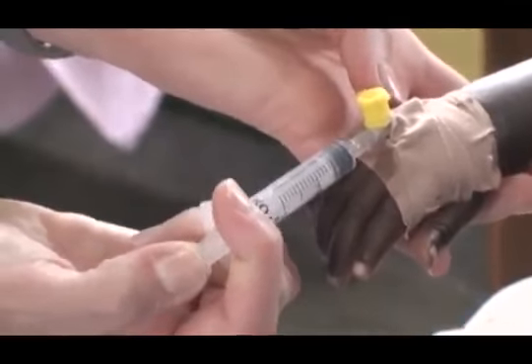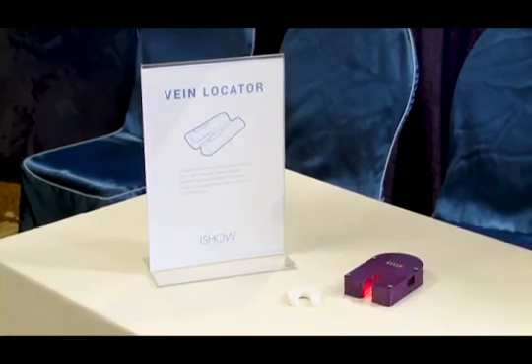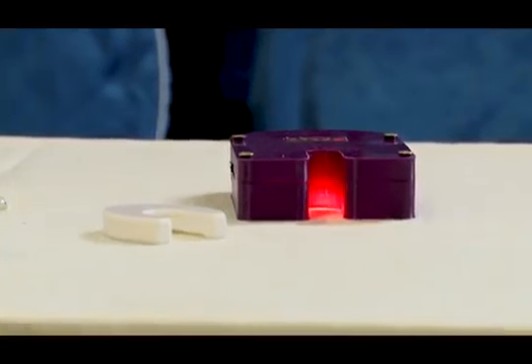The prototype was heating, so they told us for babies we should find a way of eliminating the heat. This is a device that will be put on several babies, so we should make it from material that can easily be disinfected. They also told us babies are not simple people to work with — they always flap and fly around. It would really be nice to make this device from very strong materials so that even when it drops it can keep working. Nobody has something like this out, so this could be your uniqueness.